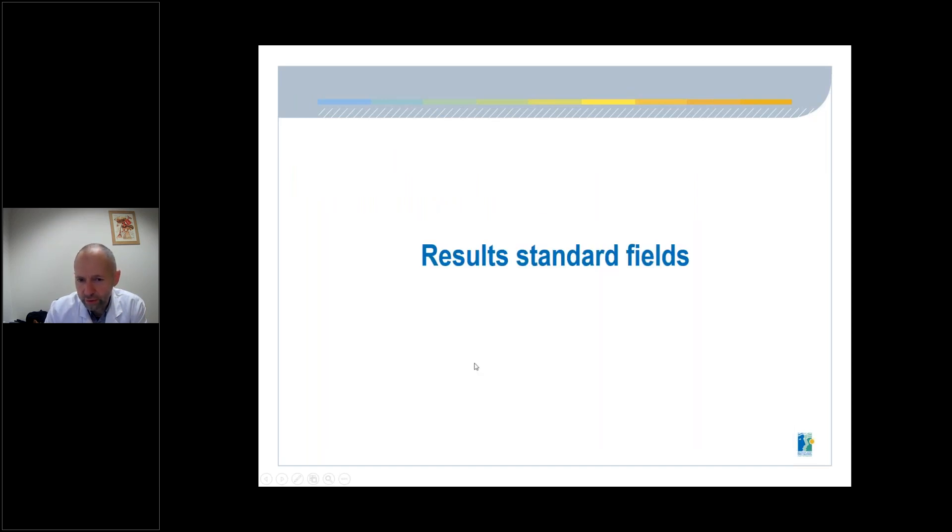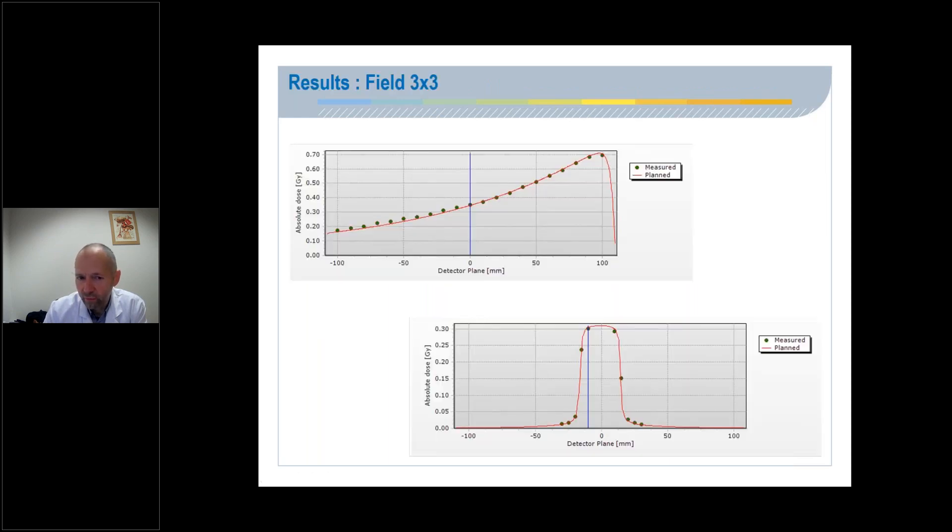What are the results obtained for the standard fields? For the 3x3 fields, results show a good agreement between measured and planned dose for PDD and for dose profile.